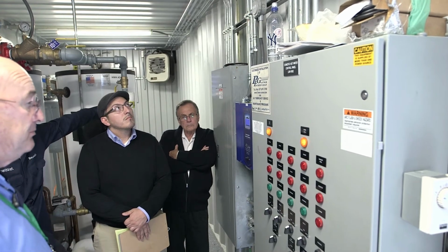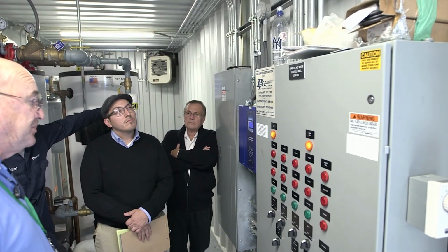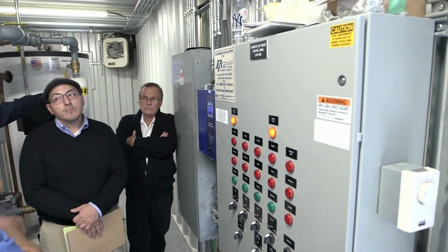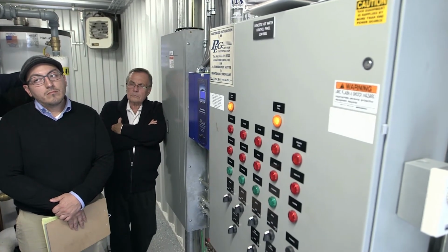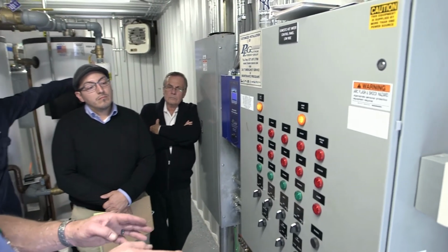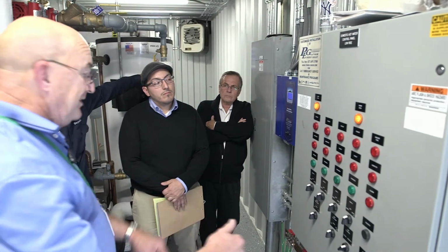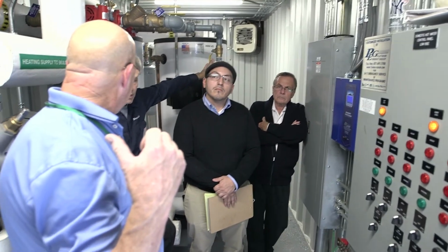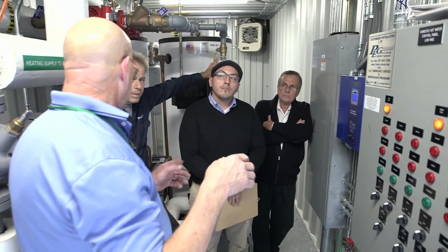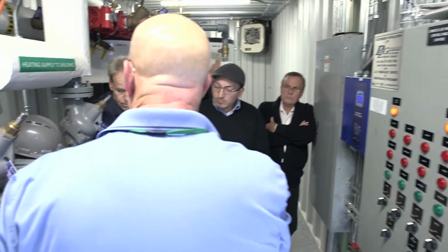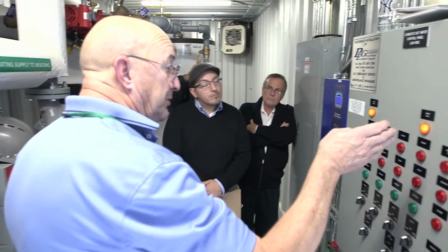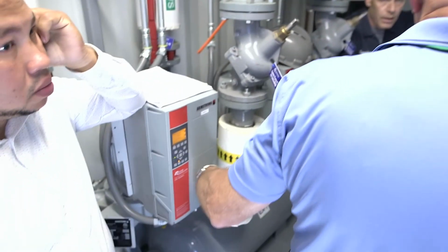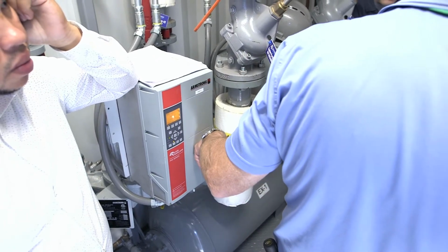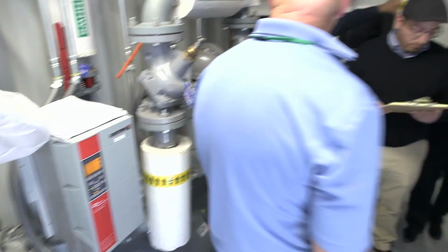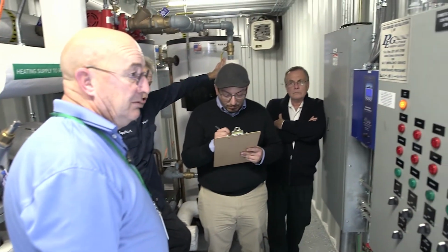That's what you're seeing with the domestic call. Domestic call, you'll hear the pumps kick in. When the pumps come up to speed, it tells the panel we're ready, turns the boiler on. Same thing with the heat pump. You see the BMS call? The pump's going to start up. The boiler's not going to come on right away. This has to come up to speed, and then the boiler will come on.